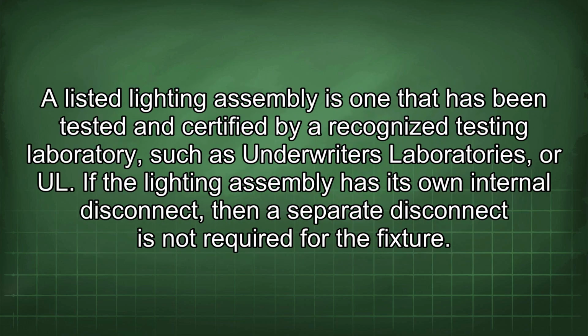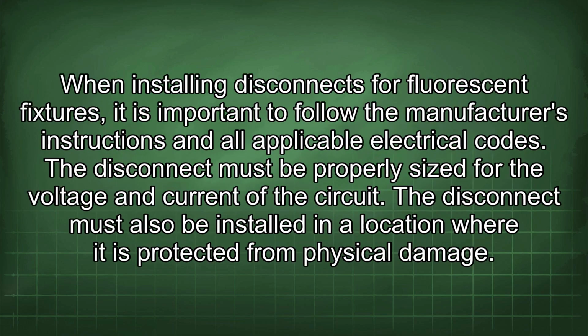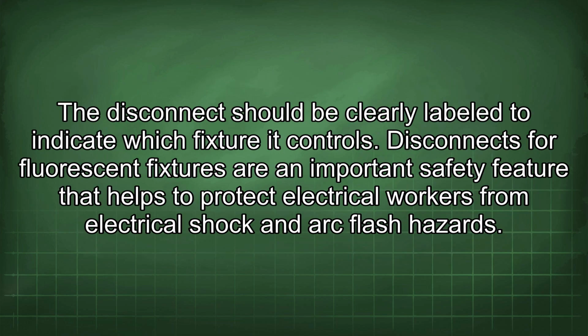A listed lighting assembly is one that has been tested and certified by a recognized testing laboratory, such as Underwriters Laboratories, or UL. If the lighting assembly has its own internal disconnect, then a separate disconnect is not required for the fixture. When installing disconnects for fluorescent fixtures, it is important to follow the manufacturer's instructions and all applicable electrical codes. The disconnect must be properly sized for the voltage and current of the circuit. The disconnect must also be installed in a location where it is protected from physical damage. The disconnect should be clearly labeled to indicate which fixture it controls.